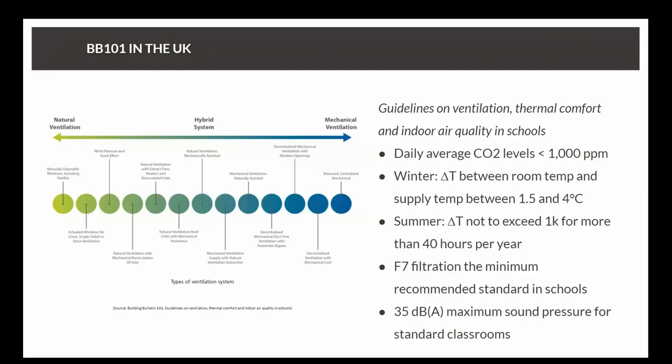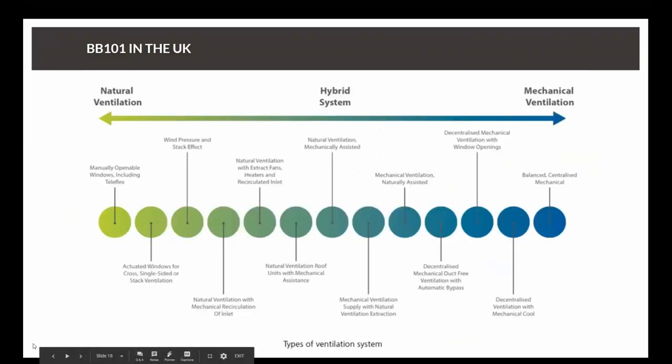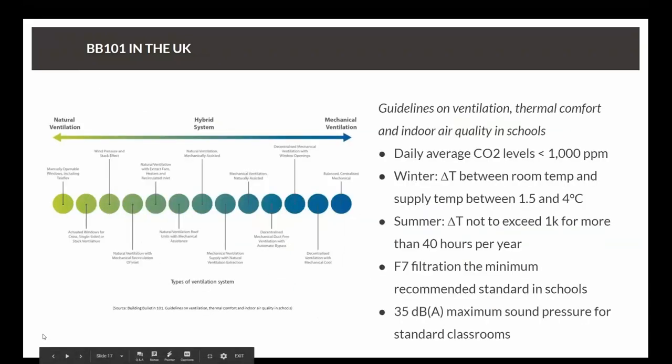Finally in the last year this was recognized and led to a reissue of BB101. BB101 is the guidelines on ventilation, thermal comfort and indoor air quality in schools. To give you a brief overview of what that involves, you can see a number of points here on the screen. Whilst we previously just looked at flow rates, we're now looking at predetermined CO2 levels that we need to achieve. We also have requirements on the temperature difference between supply air and room air, filtration standards at F7, specific delta T requirements for summer, and sound pressure levels.